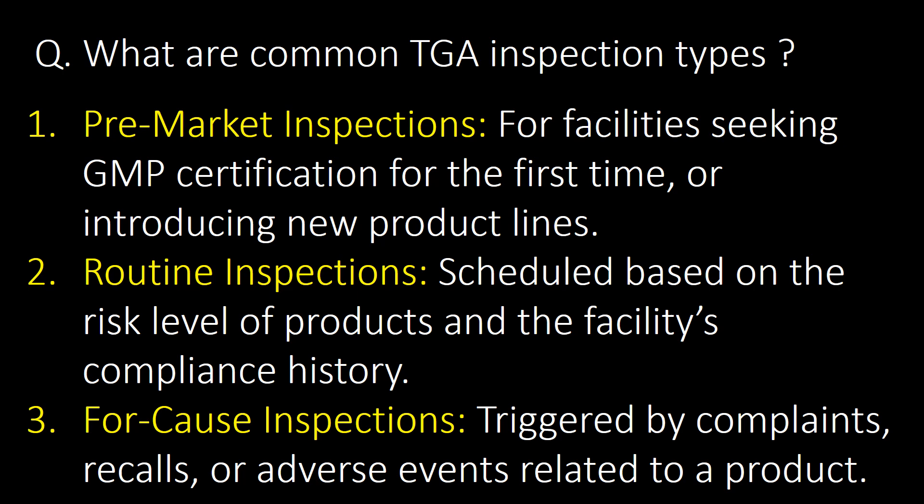What are the common TGA inspection types? The first type is pre-market inspection for facilities seeking GMP certification for the first time or introducing new product lines. The second type is routine inspections, scheduled based on the risk level of products and the facility's compliance history. The third type is for-cause inspections, triggered by complaints, recalls, or adverse events related to the product.